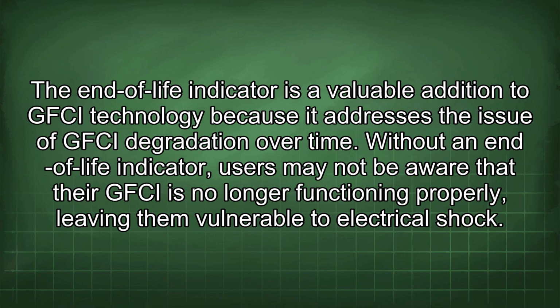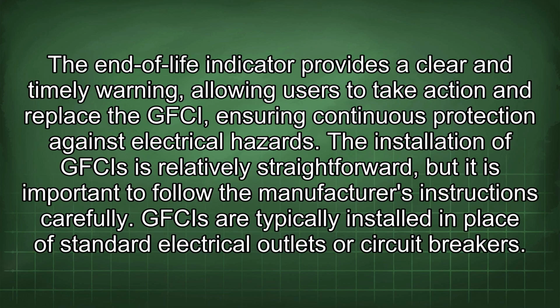The end-of-life indicator is a valuable addition to GFCI technology because it addresses the issue of GFCI degradation over time. Without an end-of-life indicator, users may not be aware that the GFCI is no longer functioning properly, leaving them vulnerable to electrical shock. The end-of-life indicator provides a clear and timely warning, allowing users to take action and replace the GFCI, ensuring continuous protection against electrical hazards.